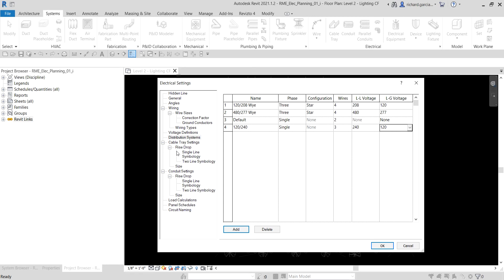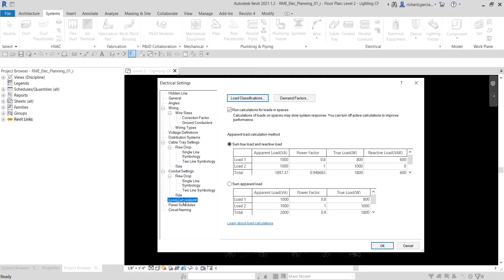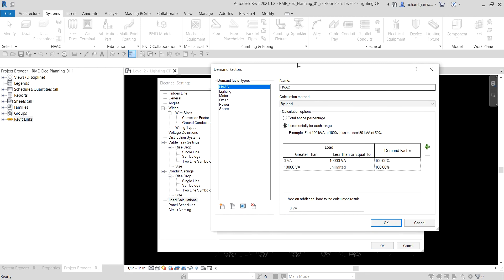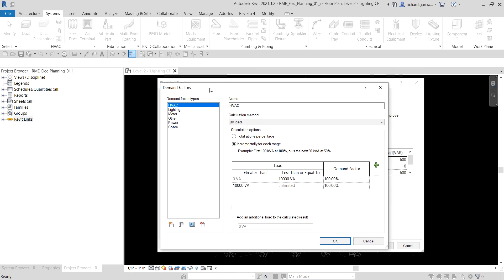The last part to cover is demand factors, which are found under Load Calculations. We use demand factors to adjust the rating of the main service for a building based on the expectation that at any given time not all the electrical equipment will be drawing at full rated load.